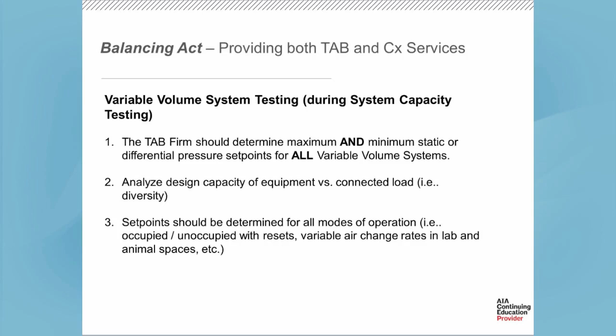So on the air handling unit side, what should the TAB firm do to dovetail with what we're talking about here? It really comes down to just verifying sensors and base functionality of components. It's not going through and doing sequencing. We're going to handle that in the functional performance testing, but it's getting everything ready to make sure that the components work before functional testing occurs on the commissioning side. And so it's verify the calibration, put in offsets and record those offsets, and work with the controls vendor to do that. And then also verify correct operation of all points.